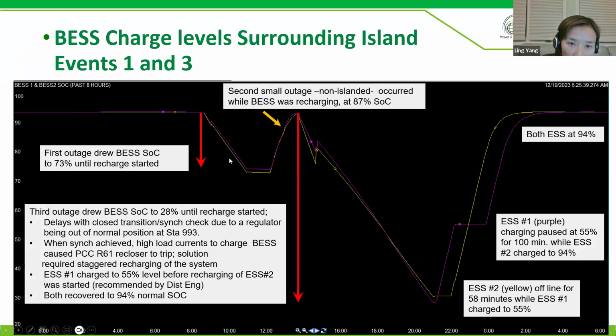The battery starts discharging, and somewhere after the first event, I think the battery system was woken up and then recharged. The operators connected the BESS and resynced it back to the system and charged again. And then the following fault came, and because of the following faults, the battery starts to discharge again.